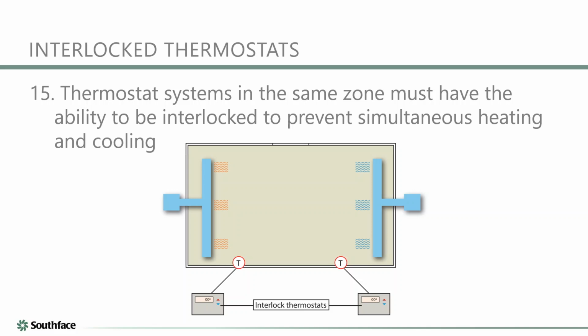All right, another thermostat related requirement. Thermostats that serve the same zone must be interlocking. And as you can imagine, this is because you don't want to have one thermostat in heating mode and another thermostat in cooling mode, just duking it out with each other to see who wins the space. Does that sound efficient? No, of course not. It sounds terribly inefficient. Plus you're going to roast some people and freeze some people, right? So, all joking aside, this requirement is very straightforward. You can understand why you don't want to set thermostats servicing the same zone, one to heating mode and one to cooling mode. And this just says you should have the equipment interlocked in a way that that's not functionally possible.